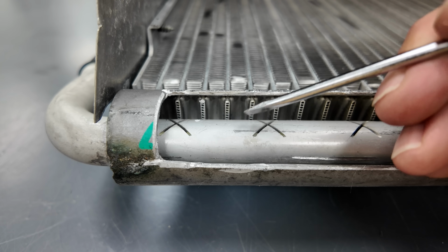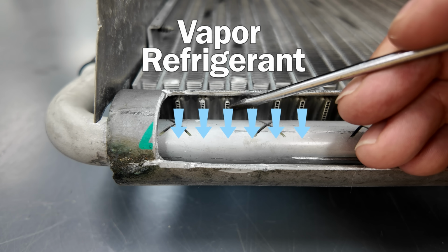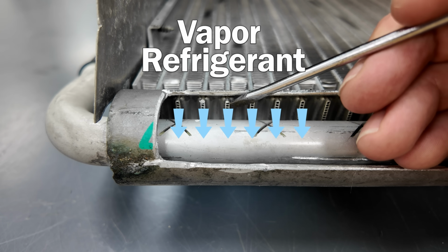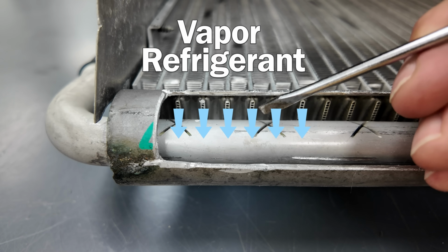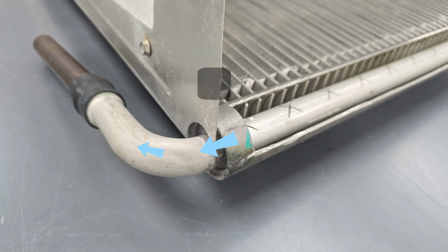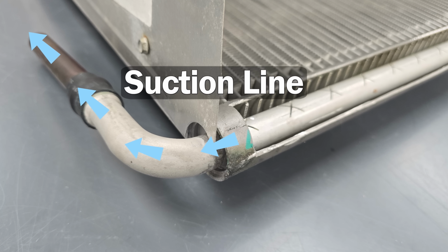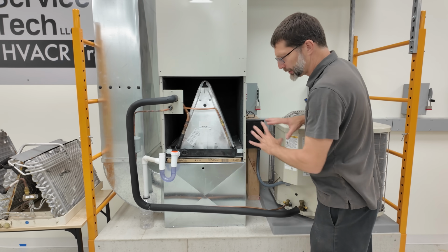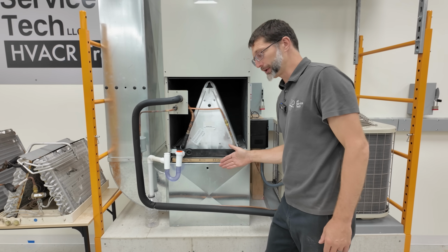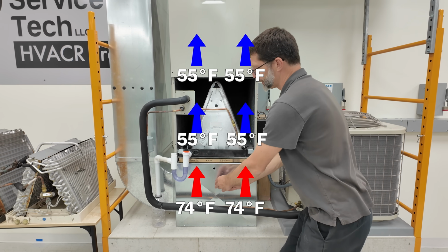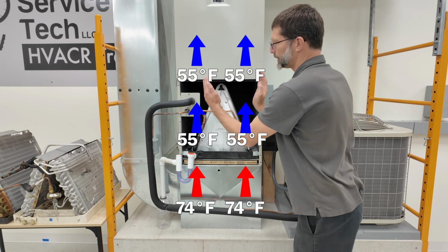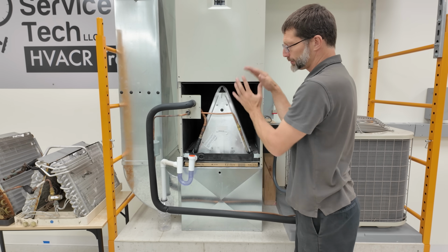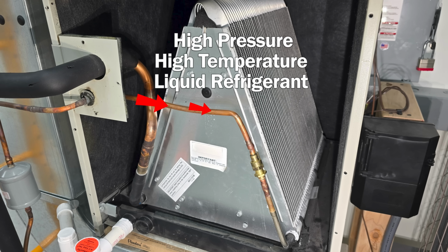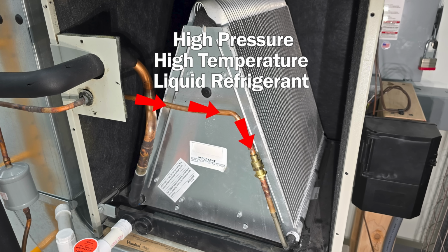On the vapor suction side of the coil, we have the vapor refrigerant exiting through each of these little microchannels, entering into the header, entering through the little slits into the suction line where it's then going to exit the coil. Now when the coil is connected to a whole system, obviously you'd have to have the door here because you're going to have air going through the coil fins and traveling up to the blower and out of this air handler that we have here.